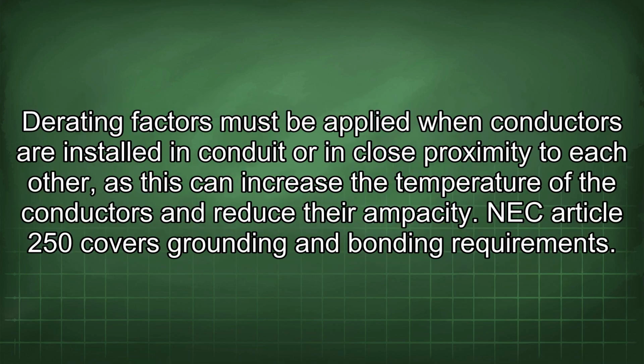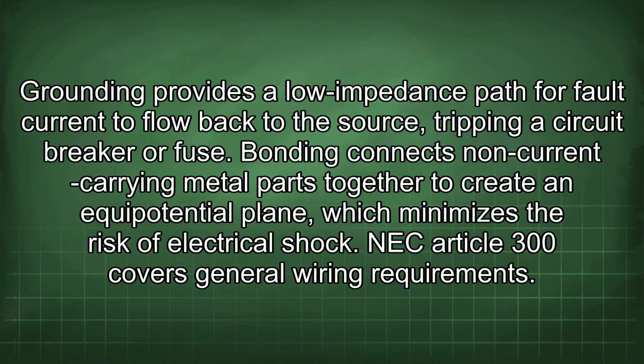Derating factors must be applied when conductors are installed in conduit or in close proximity to each other, as this can increase the temperature of the conductors and reduce their ampacity. NEC Article 250 covers grounding and bonding requirements. Grounding provides a low impedance path for fault current to flow back to the source, tripping a circuit breaker or fuse. Bonding connects non-current carrying metal parts together to create an equipotential plane, which minimizes the risk of electrical shock.